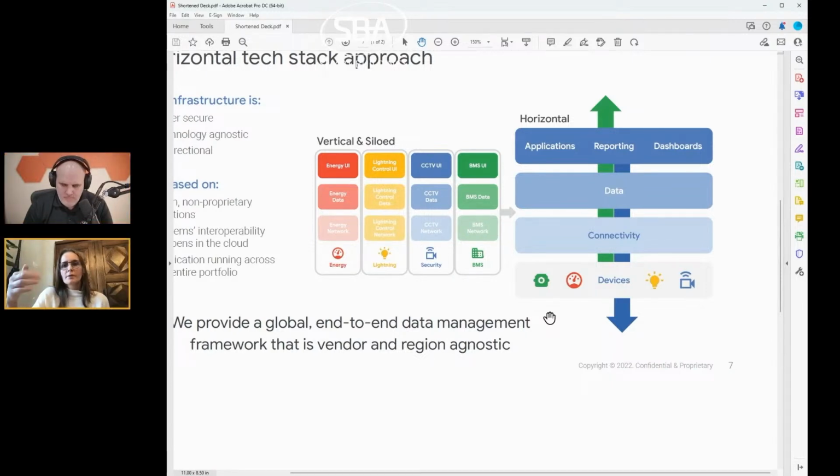As far as the model goes, the more data layer aspect of it, we work with a master systems integrator. So basically in new construction, we have a digital building consultant and a master systems integrator. The digital building consultant understands what use cases need to be supported for a specific building, right? There's flexibility at the building level. So the consultant does their own analysis or interviews and understands what this building needs to accomplish. From that, they figure out what data points need to be pulled, which devices need to be installed, which data points are of interest.